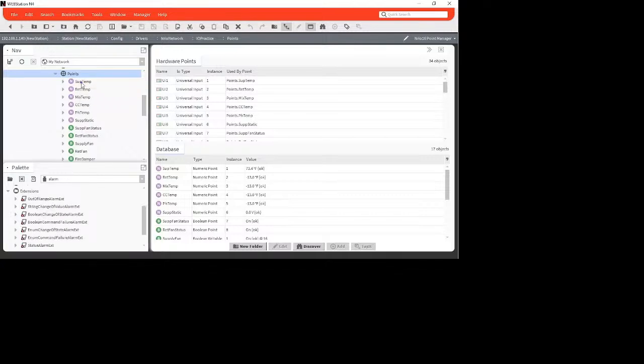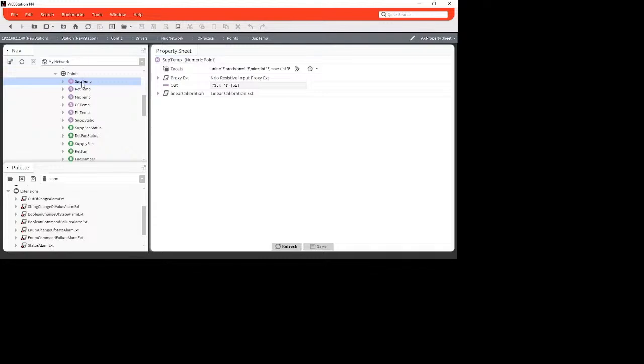We're going to put the alarm extension on our temperature, our supply temperature. We will use this as a test. So you simply take the out of range alarm extension and drag it and drop it on your sensor. Then you will see it underneath, or if you drop down in your sensor, you will see out of range alarm.